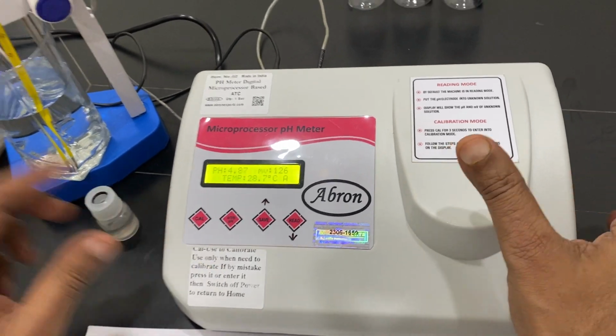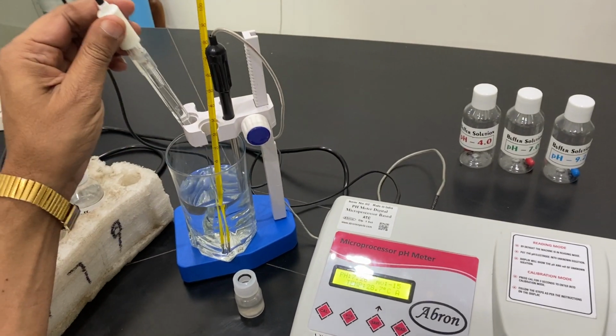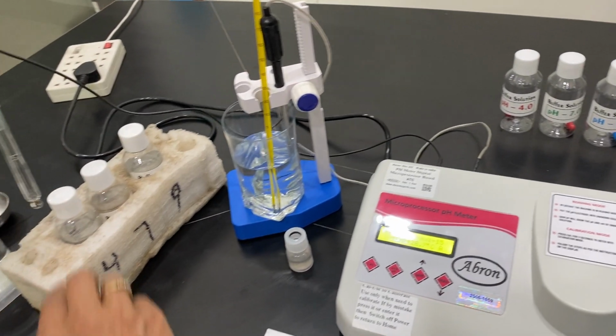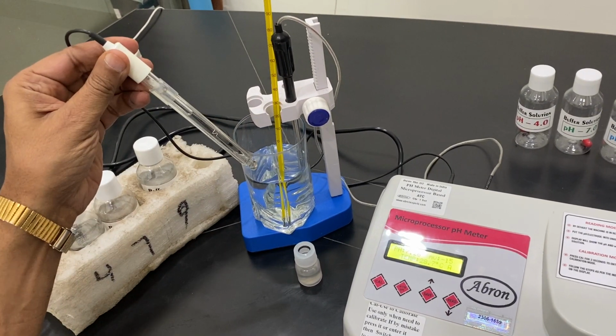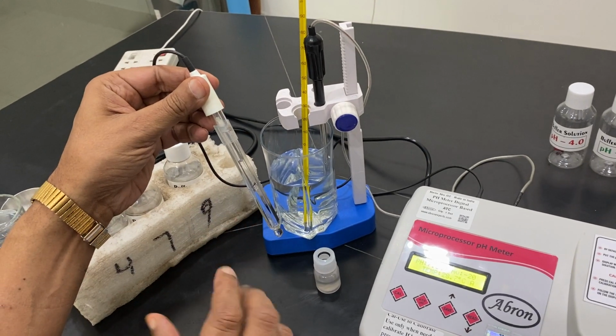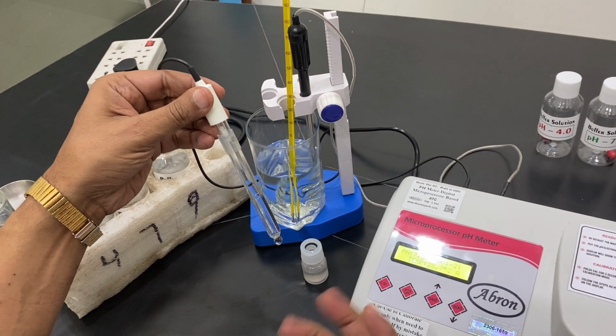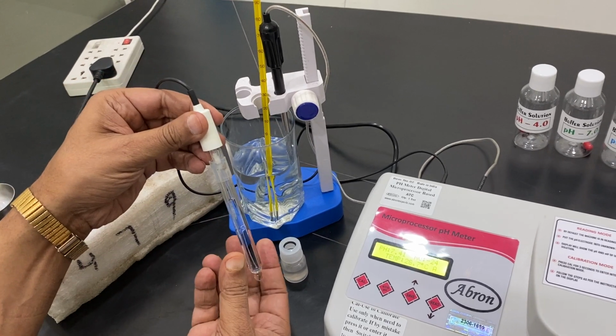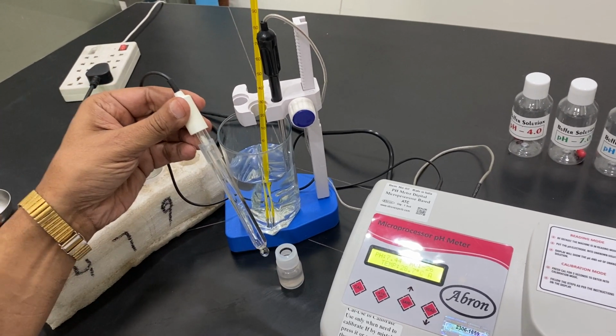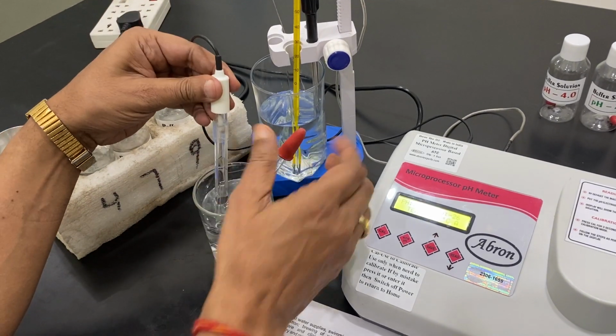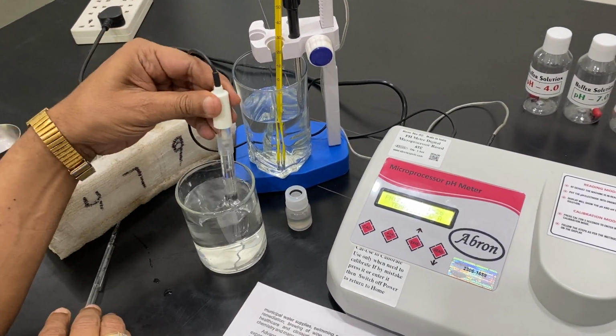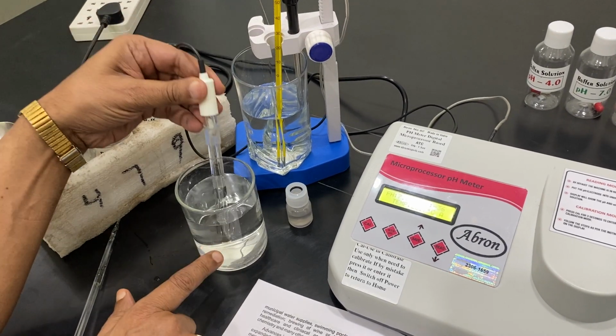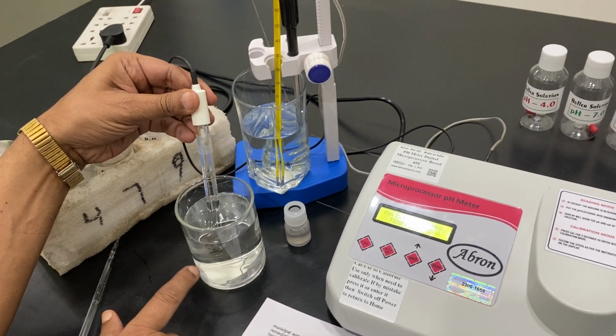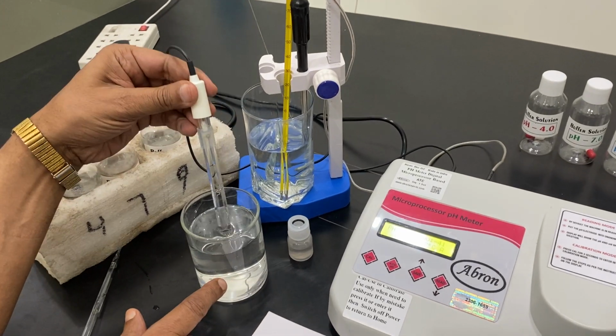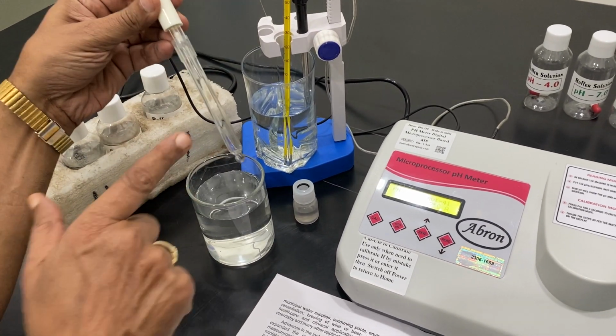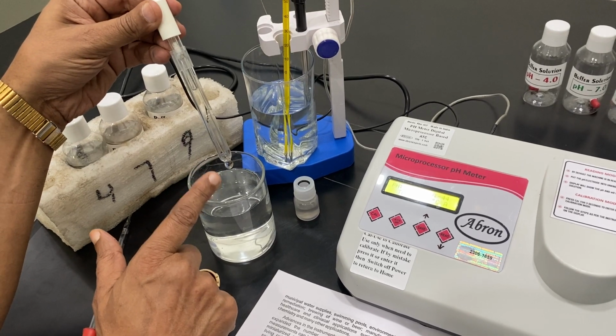The next problem is that the electrode is dipped from one solution or any other solution directly into the testing solution. No, it should always be washed with running water from the wash bottle, and then the tip should be wiped. It should be dipped about 2-3 times slowly in water and rinsed very carefully. The tip can break, so it should not touch the glass part. So be very careful. This is the second problem.